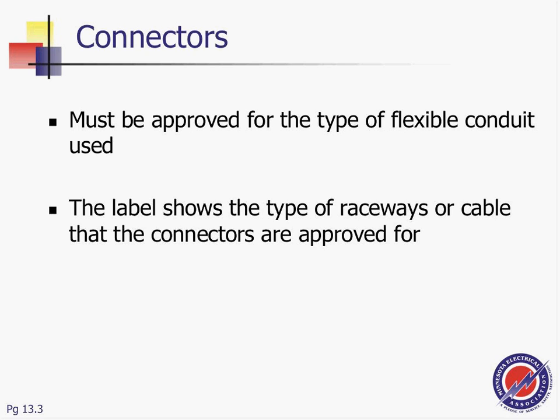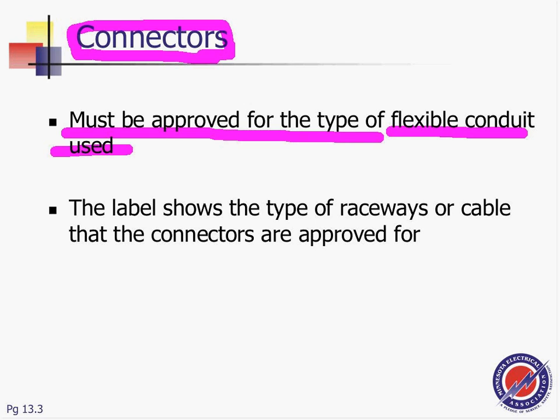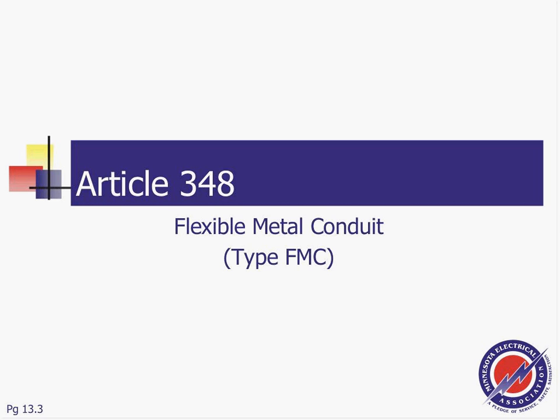Okay, connectors must be approved for the type of fitting. You can't use an EMT connector with a flex. Flex has its own designed connectors. So you have to have listed connectors that go with the flex. That we all know. The listing shows the type of raceway or cable that the connector is approved for. All conduits, guys, have their own listed connectors that go with them. I can't mix EMT with MC cable and so forth. So that's the key point before we jump directly into flexible metallic conduit.